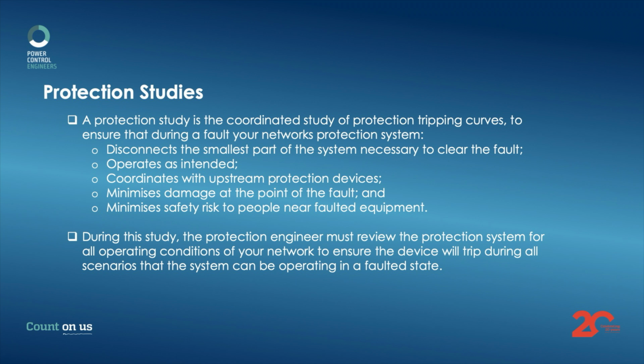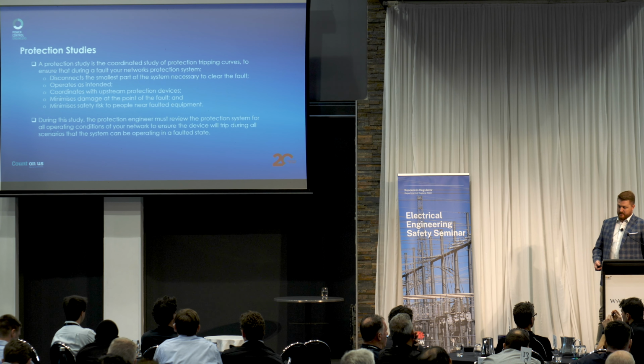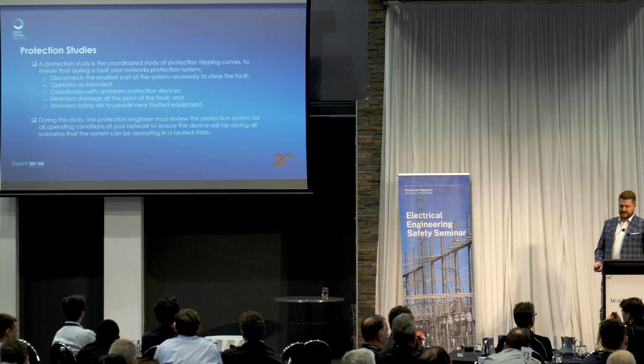Protection studies. So protection studies is the coordinated study of protection tripping curves to ensure that during a fault your network's protection system disconnects the smallest part of the network necessary to clear the fault, operates as intended, coordinates with upstream protection devices, minimises damage at the point of the fault, and minimises safety risk to people near faulted equipment. So during this study, the protection engineer must review protection systems for all operating conditions of your network to ensure that the device will trip during all scenarios that equipment can be operated in a faulted state.